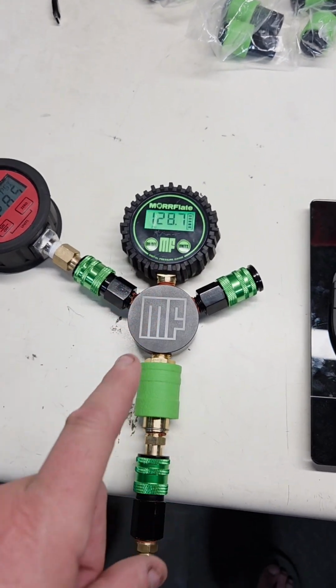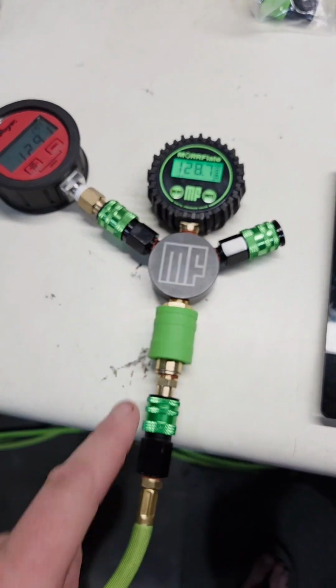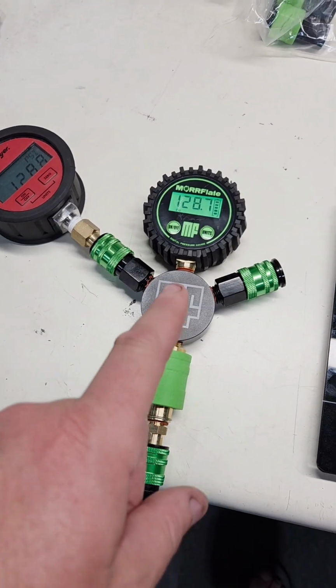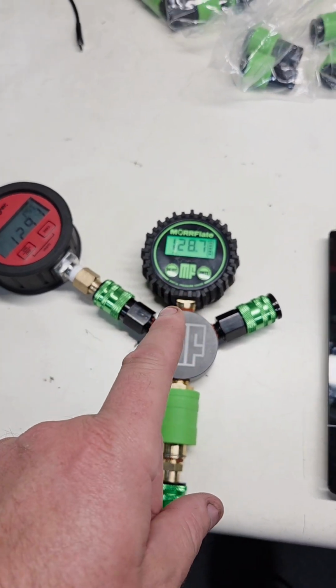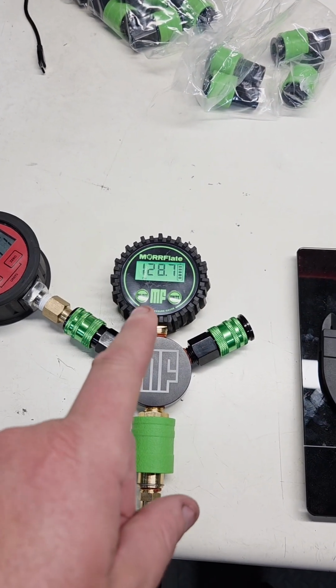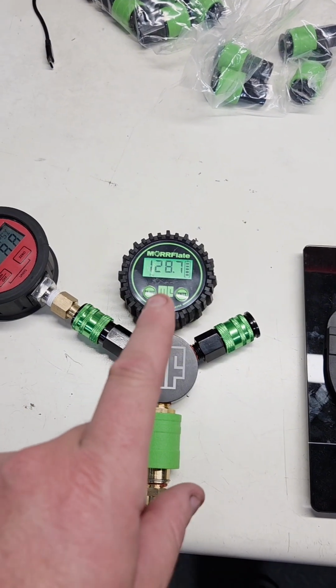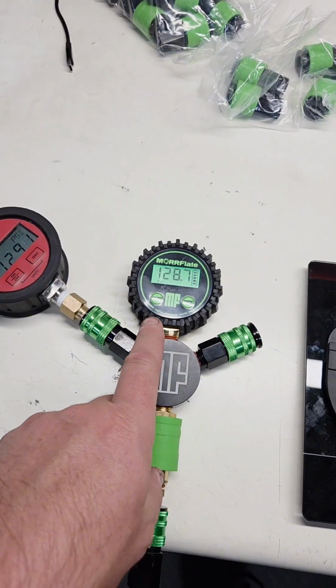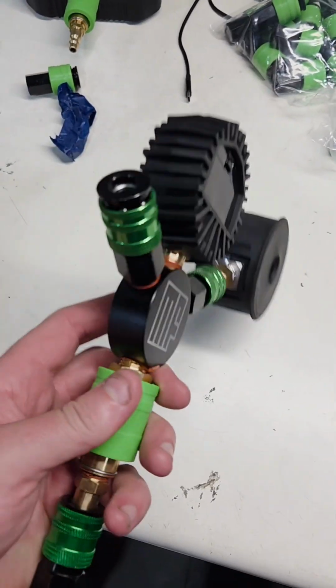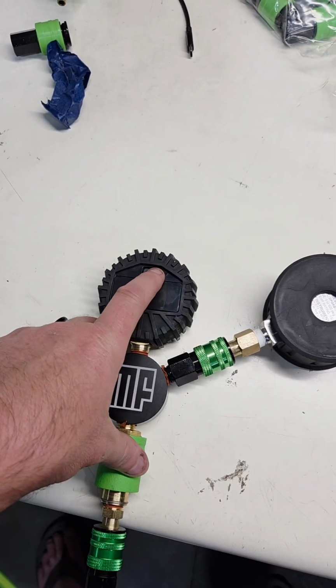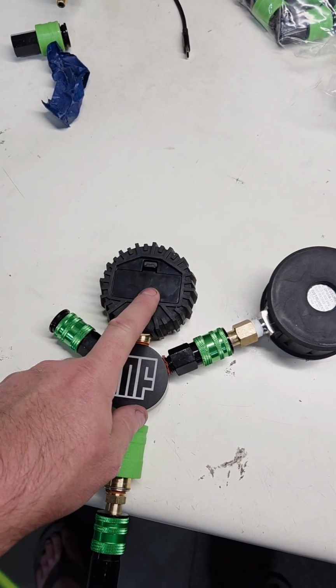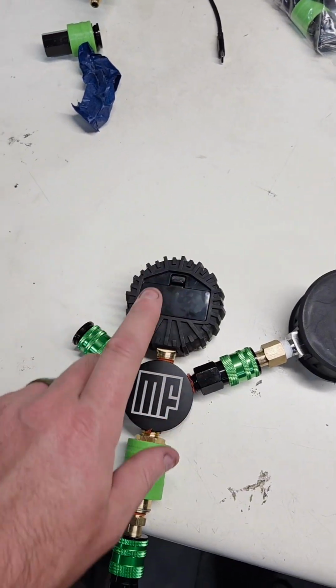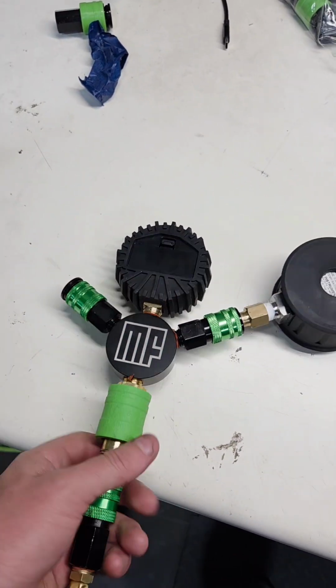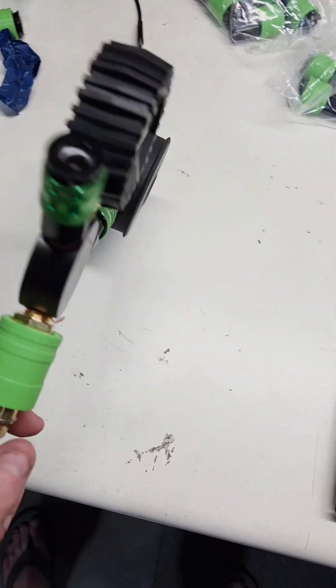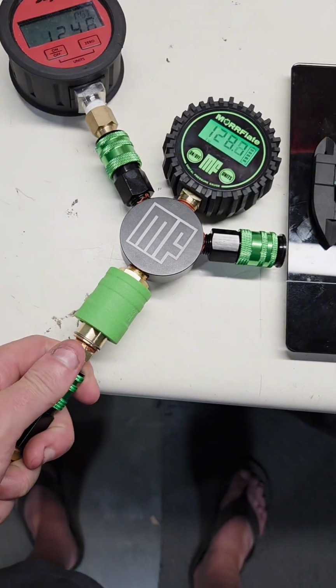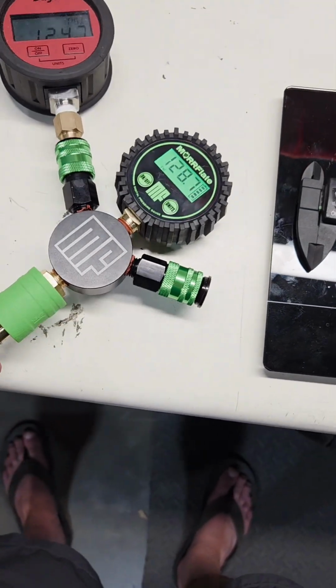So what happens is if you turn on the gauge with air pressure in the system and the gauge pressurized, there's a very high chance it is going to throw off the calibration of your gauge. To reset your calibration, all you need to do is take out the batteries here. When you take the batteries out the back of the gauge, this is hard to do with one hand, so I'm not going to do it, but take the batteries out of the back of your gauge. That'll have power off. And then what you really need to do is disconnect your gauge from any air source.